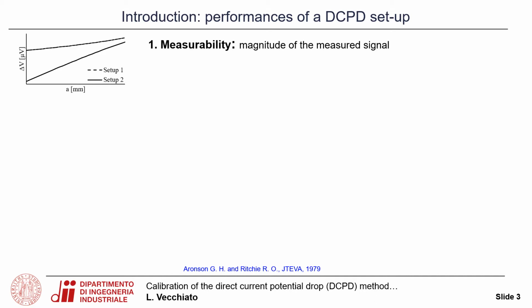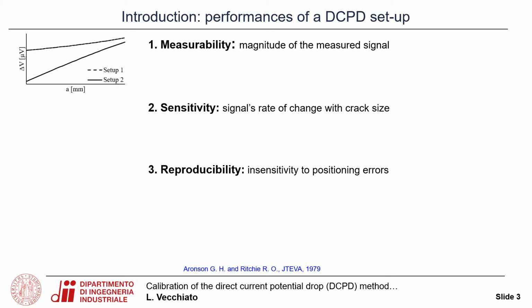Aronson and Ritchie proposed 4 parameters. The first is the measurability, which means the magnitude of the measured signal. The second is the sensitivity, which is the rate at which the signal changes with the crack size. The third is the reproducibility, which gives information about the insensitivity of the signal to unavoidable positioning errors of the probes. And the last is the accuracy, which gives information about the degree at which the calibration curve is representative of the real crack size and shape.